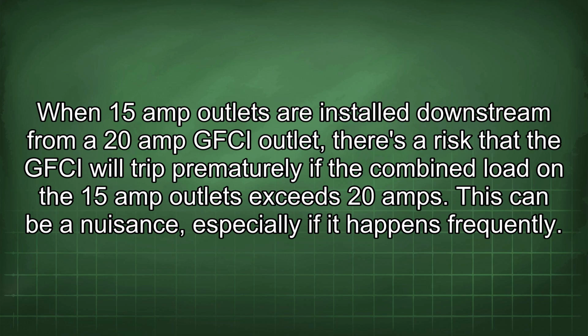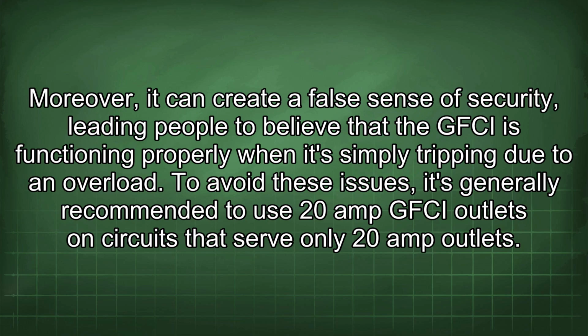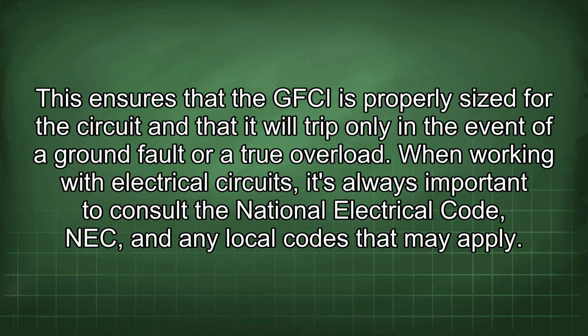This can be a nuisance, especially if it happens frequently. Moreover, it can create a false sense of security, leading people to believe that the GFCI is functioning properly when it's simply tripping due to an overload. To avoid these issues, it's generally recommended to use 20 amp GFCI outlets on circuits that serve only 20 amp outlets. This ensures that the GFCI is properly sized for the circuit and that it will trip only in the event of a ground fault or a true overload.